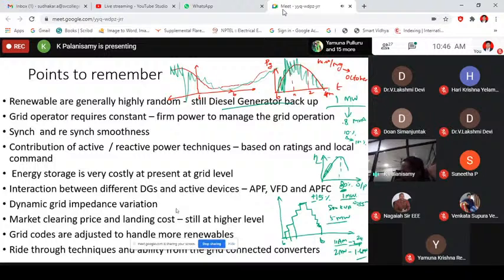See, when you buy an active power filter to take care of 5th and 7th harmonics or some other harmonics, and also to supply reactive power, normally you should give the proper information to the APF, active power filter, supplier, right? Because when we have more, for example, VFDs, variable frequency drives, right? That too, 6-pulse rectifier based VFDs. So 6-pulse rectifiers definitely will have characteristic harmonics of 5th and 7th, right?